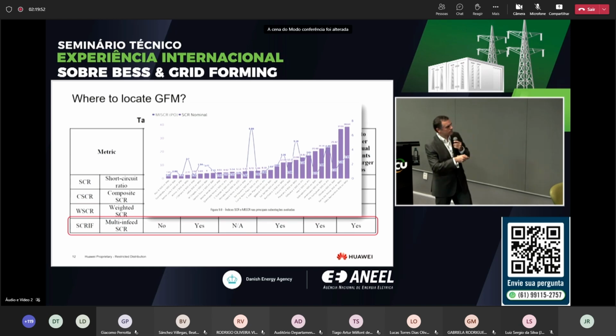So in the end, the message is that by considering this mutual interaction short circuit ratio, we can identify the buses that have a lot of power electronics around affecting the voltage. In those buses, we can think about synchronous condensers, which we're very sure will work since it's a 100-year-old technology. But if there are batteries around, and we put grid forming in those batteries, we can save all the cost of the synchronous condenser. That's the main point.